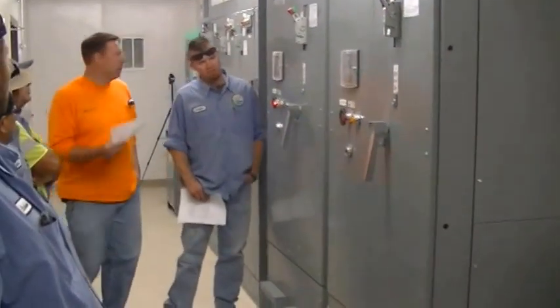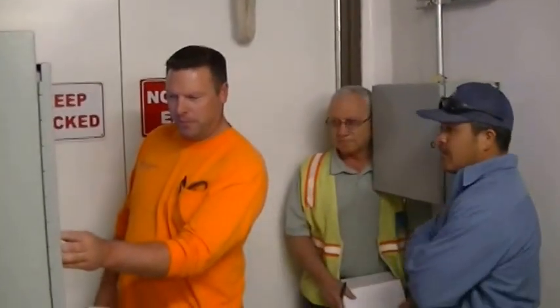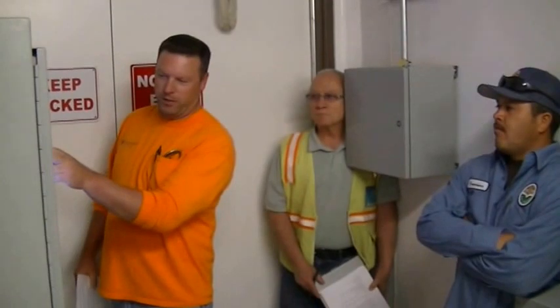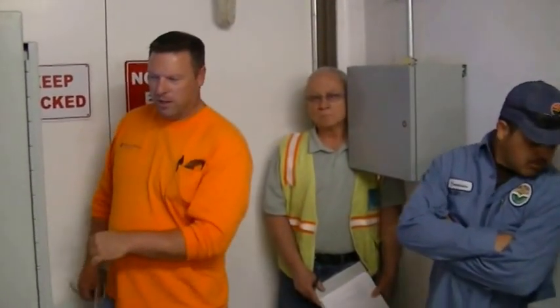One thing I want to elaborate on, the power meter. Since your last training on HMI, some of that power meter information has been added to the HMI on the RTU cabinet also. I know it's kind of hard for everyone to get over here. But if you come under the utility button, and you come into power, it'll also show you everything that's up there in that power meter. So it shows you your current amps in all three phases, your voltage, how many kVA we're using, power factor, so that's just another interface for the power meter. And it's probably a lot easier to read over there.